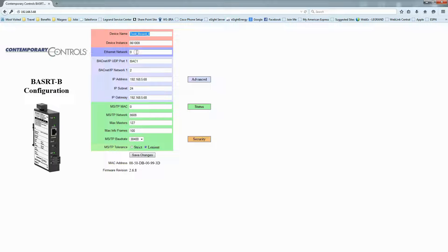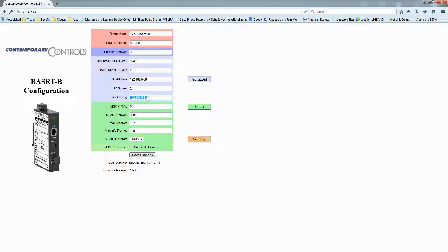You can see I've given it a device name — test board 8 — and a unique device instance. The UDP port is BAC1, which is also 47809, and the BACnet IP network number is 2. These settings will also match in the segment manager configuration. The subnet gateway matches the IP address because there's no actual gateway on this network. It also has a unique MSTP network number set to 8608. You can save changes, which will also effectively reboot the NB router.